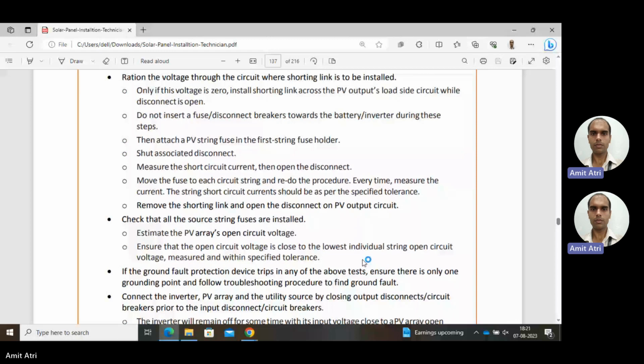So next, if the ground fault protection device trips in any of the above tests, okay, means the ground fault protection device is there, and if it trips in any of the steps which we have done for measuring the voltage and the current, that is open circuit voltage and short circuit current, then ensure there is only one grounding point and follow the troubleshooting procedure to find the ground fault. Okay, after that we have to ensure whether there is any ground fault or not. So next we have to connect the inverter, PV array and the utility source by closing the output disconnect or the circuit breaker. Whatever equipment we are using for connection and disconnection, we have to close it. Okay, and yeah, so the output disconnect circuit breaker should be closed prior to the input disconnect or circuit breaker.